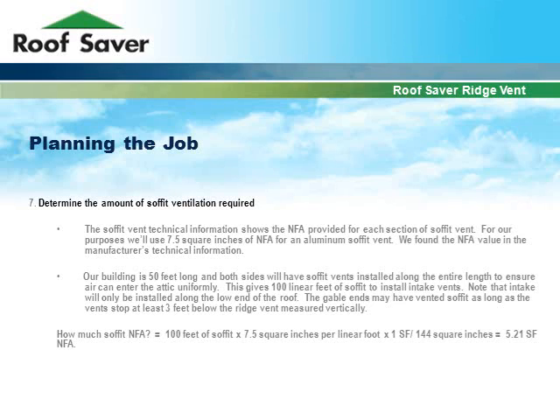The soffit vent technical information shows the net free area provided for each section of soffit vent. For our purposes, we'll use 7.5 square inches of NFA per linear foot for aluminum soffit vent, a value found in the manufacturer's technical information. Our building is 50 feet long and both sides will have soffit vents installed along the entire length to ensure air enters the attic uniformly, giving 100 linear feet of soffit for intake vents. Intake is only installed along the low end of the roof; gable end vented soffit may be used as long as vents stop at least 3 feet below the ridge vent measured vertically. Multiplying 100 feet by 7.5 square inches per linear foot and converting gives us 5.21 square feet of net free area.